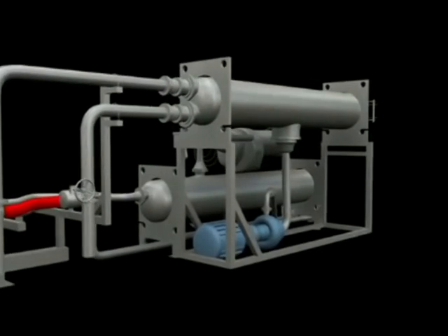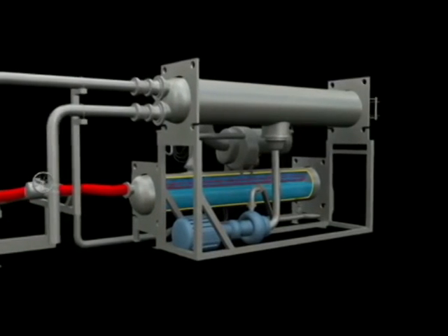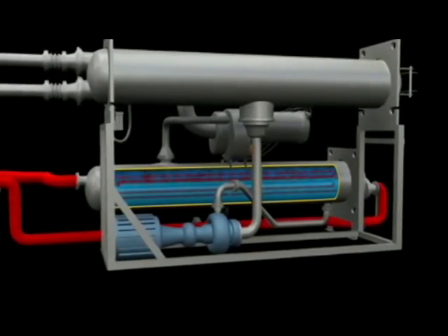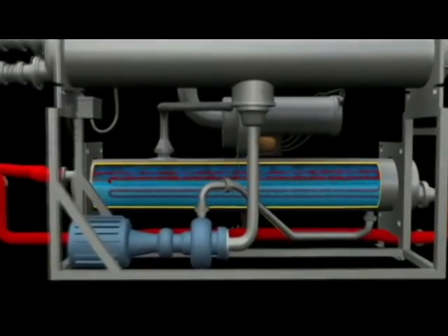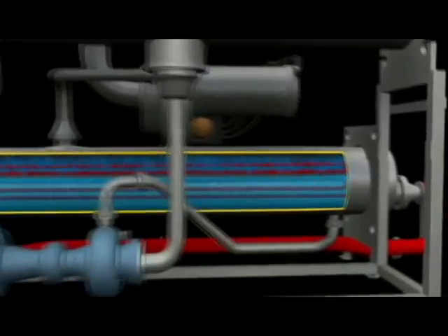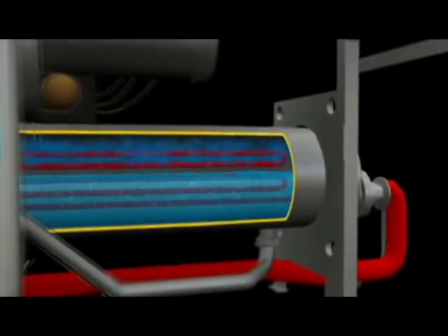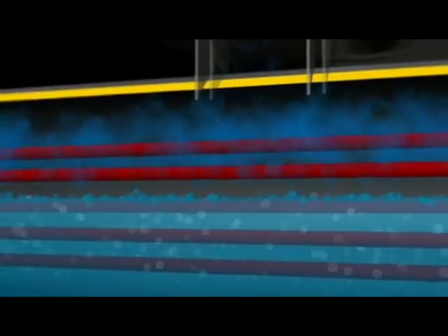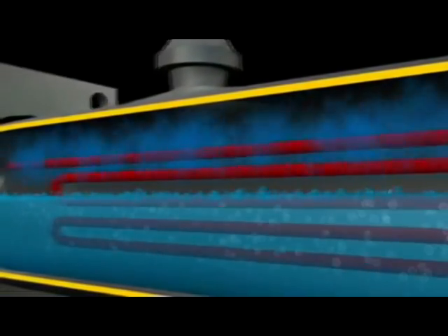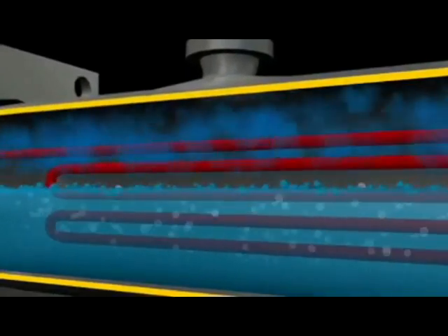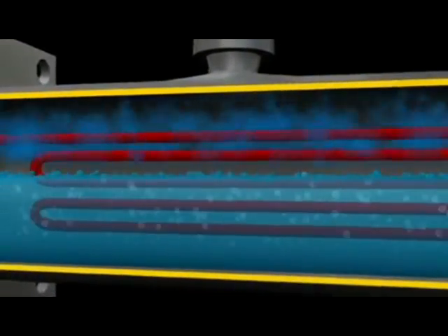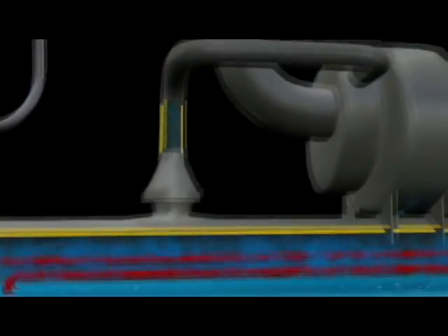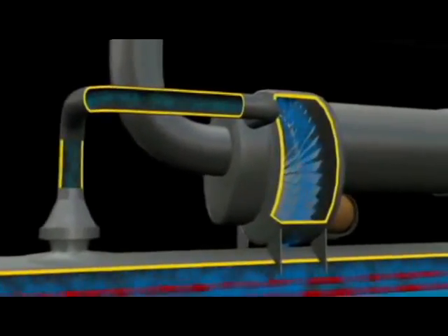The hot water enters each power generation unit. In this binary system, the well water does not come in contact with the turbine, but rather its heat is transferred to a secondary working fluid as it passes through the coils in the heat exchange tank. Because the working fluid has a boiling point much lower than water, the fluid flashes to vapor quickly and moves upward, passing through the turbine.